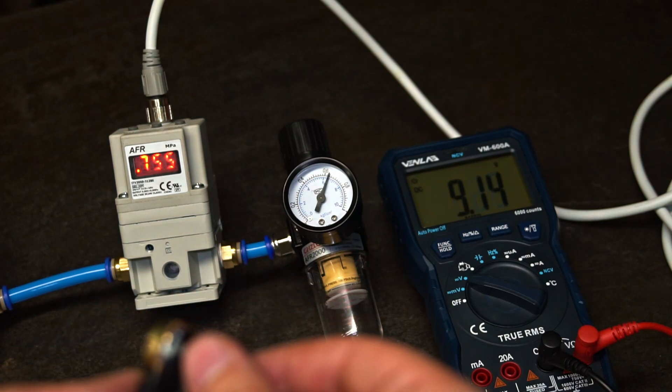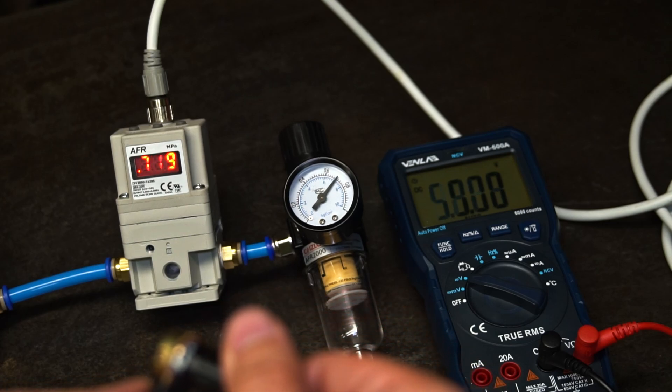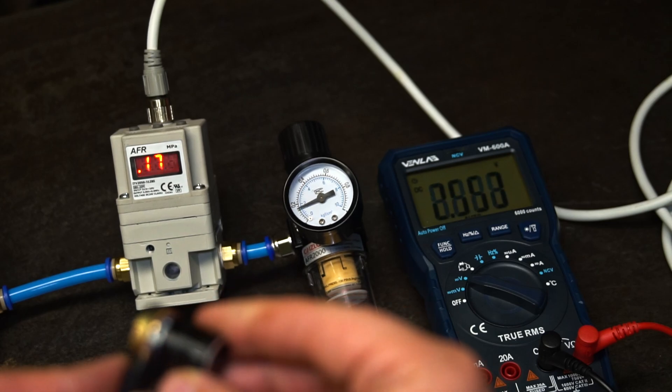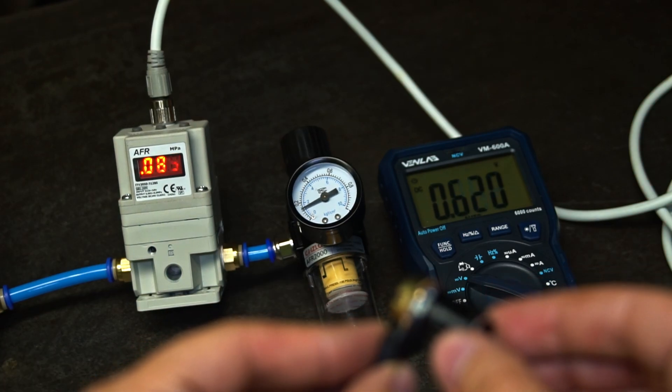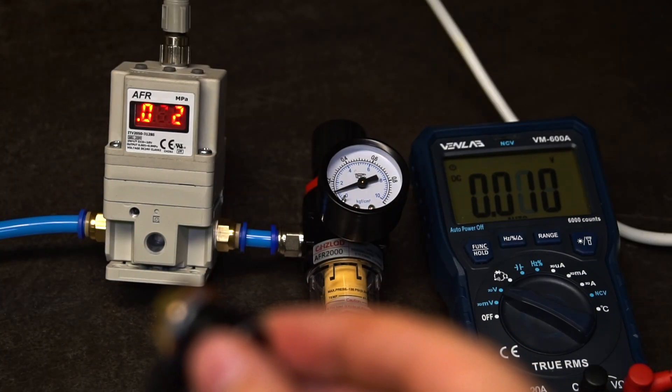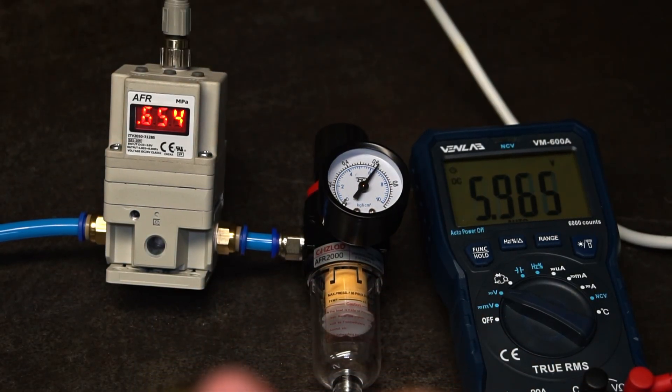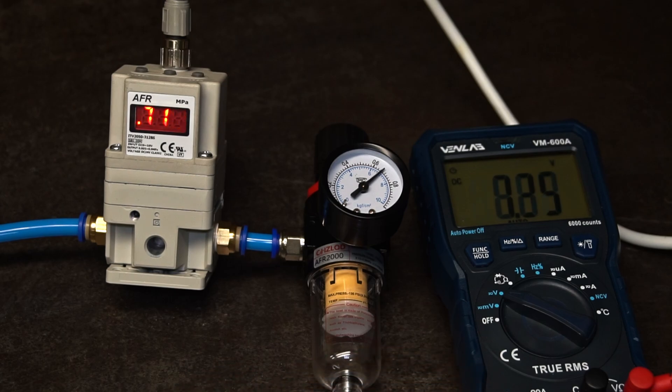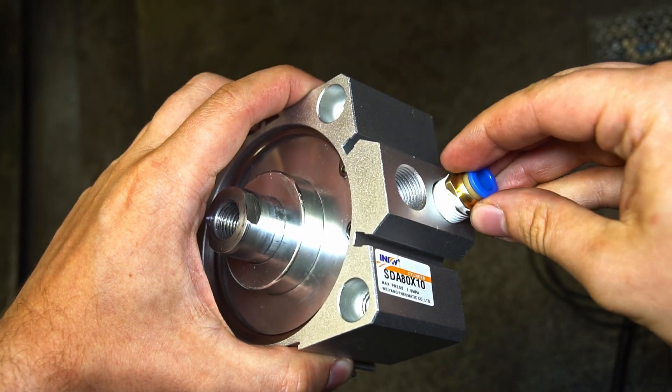At 7.6 bar at max, I guess we lose the remaining 0.4 bar somewhere between the compressor output and the regulator input. The pressure adjustment seems to be fast and accurate. If I had 10 bar on the input, I guess it would be 10 bar at 10 volts. On my settings, we get about 1 bar per 1 volt. I think we are ready for the air cylinder.